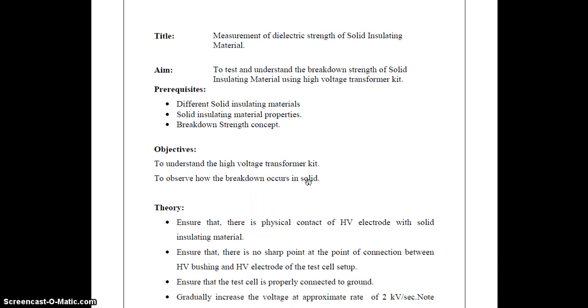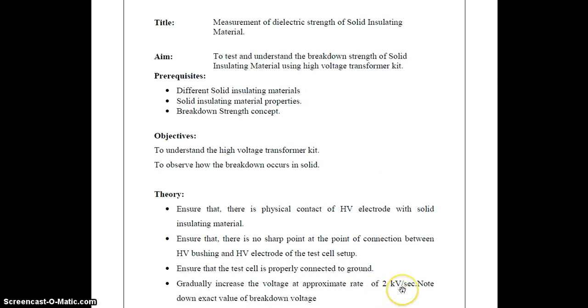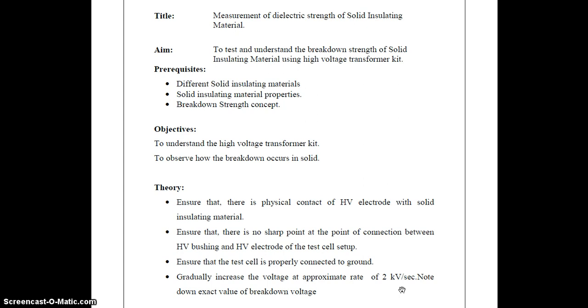theory. Ensure that there is physical contact of the high voltage electrode with the solid insulating material, meaning the solid insulating material is placed between the high voltage electrodes. Then ensure that there is no sharp point at the point of connection between the high voltage bushing and the high voltage electrode of the test cell setup. Then ensure that the test cell is properly connected to the ground. Gradually increase the voltage at an approximate rate of 2 kilovolt per second. Then note down the breakdown voltage and gap distance to find the breakdown strength. That is, breakdown strength is directly proportional to the breakdown voltage divided by the gap distance between the two electrodes.